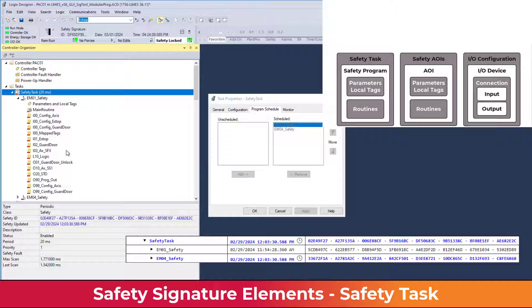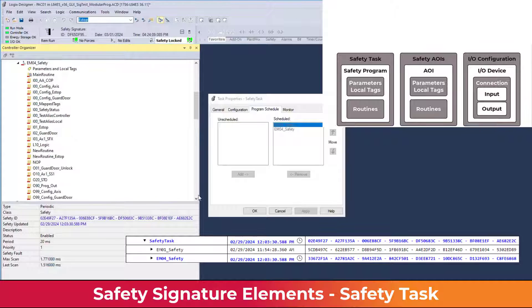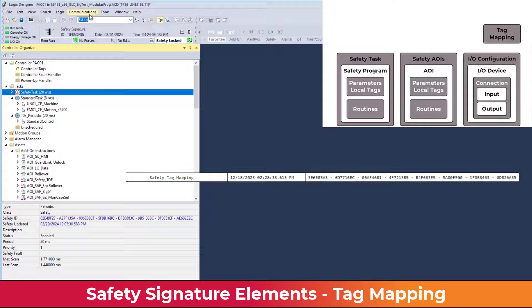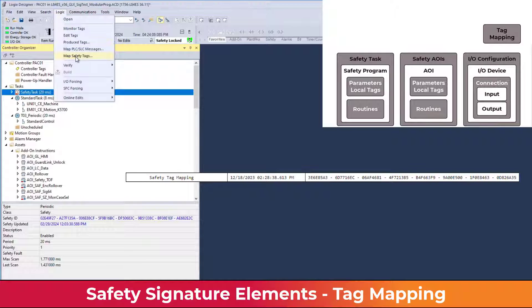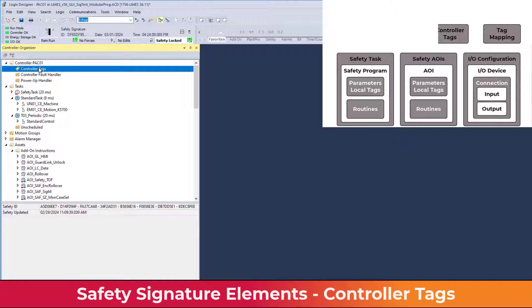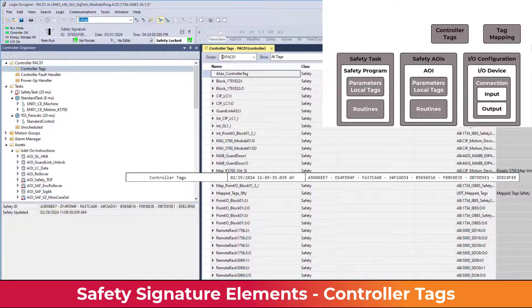This program example has modular programs for each safety section of the machine. The tag mapping signature represents the standard data being safety mapped to the safety task using the safety tag mapping found in the Logic menu — Map Safety Tags. The controller tags' safety signature represents the controller-scope safety tags, and changes to tag properties are monitored by the controller tags' signature.